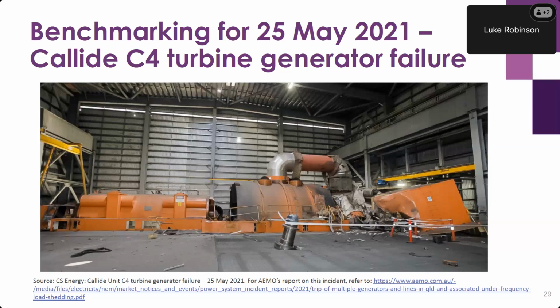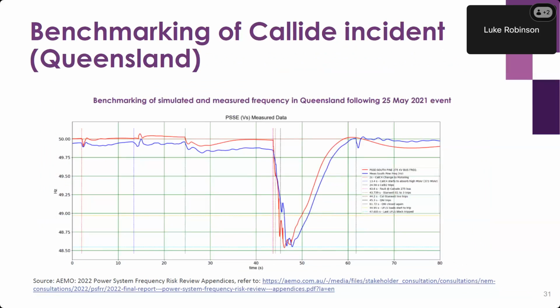This was an interesting incident, but unfortunately, discussion of all the incidents that occurred is outside the scope of this presentation. If you're interested in the specific details, you can have a look at the reviewable incident report in the link on the slide. As we can see here, we did some benchmarking of our models against the actual event, and you can see the frequency response there. The simulated and measured frequency are quite closely matched, with a difference in the frequency nadir of approximately 0.15 Hertz. I think that gives us more confidence in our models. And if we do ever find anything that doesn't align, then we have a continual improvement process for our modeling approach.